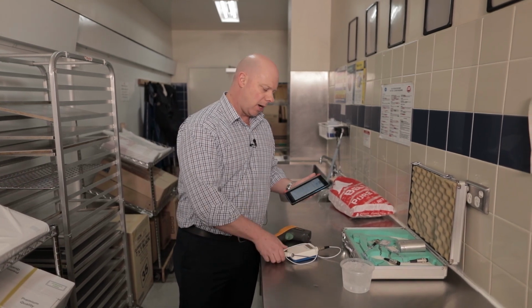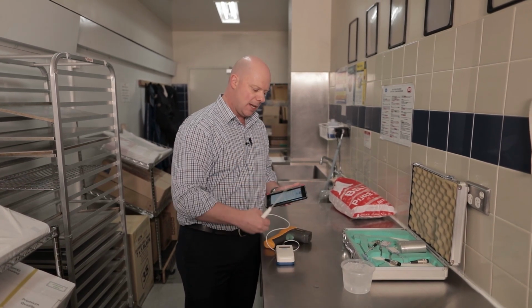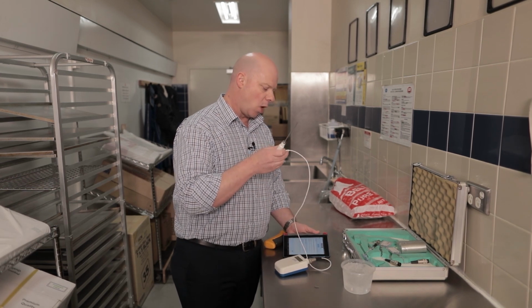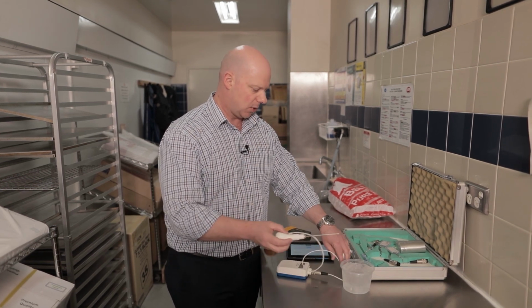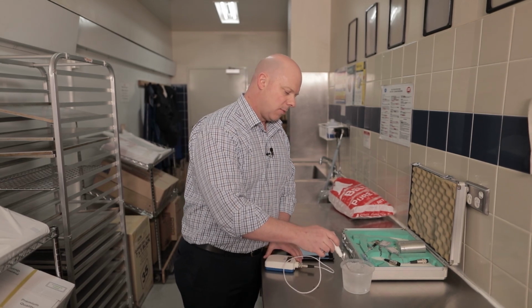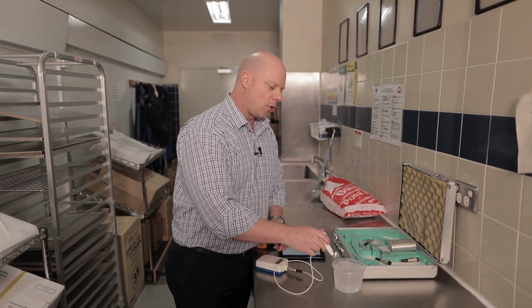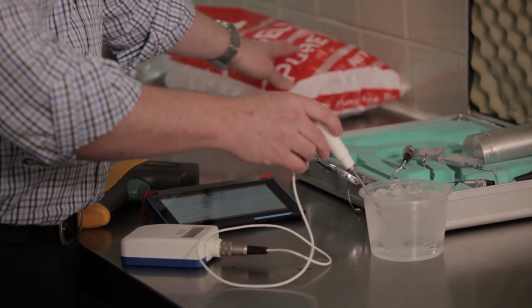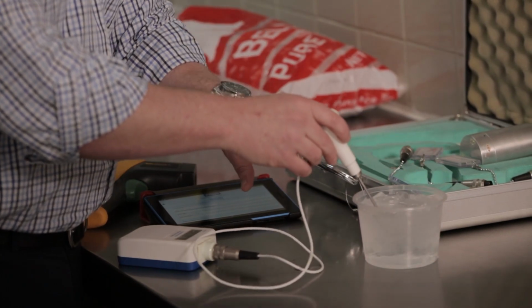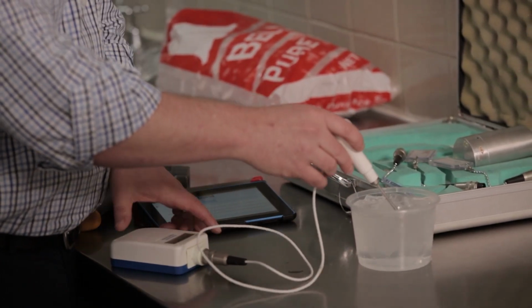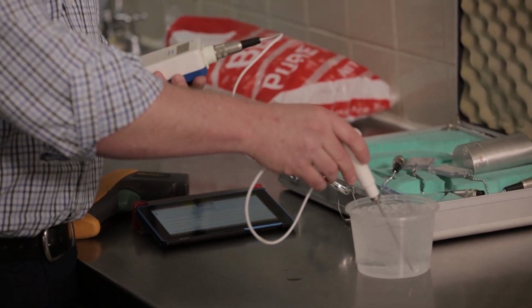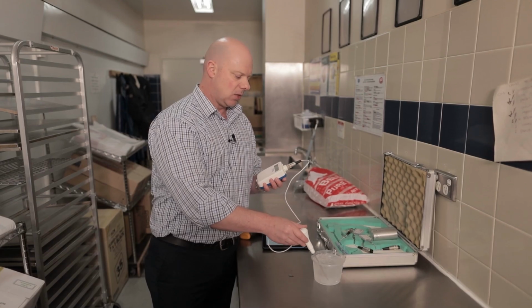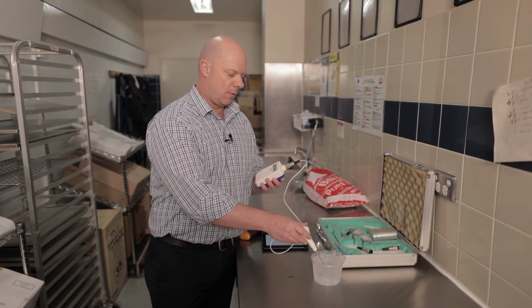So we're going to check the accuracy of this probe with the ice point check. Make sure your probe's turned on, and stick the probe into the ice water. The ice water could be crushed ice, it could be blocks of ice, it could be ice from your local supplier. All we've done is put some ice in a container and cover it slightly with water. That's what we call an ice slurry. Stir it around a bit so that the water moves around. And what we want to see is that this probe is within plus or minus 1 degree of 0.